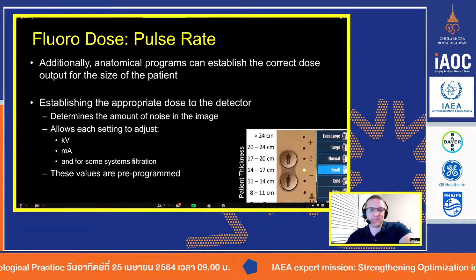So we talk about using pulse rates. The number one way to reduce dose in fluoroscopy is just not push on the pedal, right? So reducing the total amount of exposure. The second one is using these pulse rates. So here is just a little bit of math that I did. If you have 30 pulses per second as your relative 100% dose level, then everything less than 30 pulses per second is going to reduce the dose.